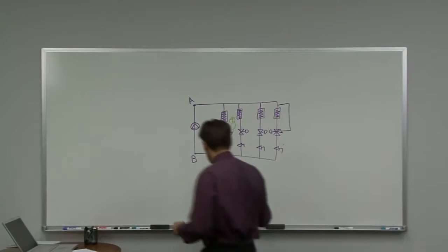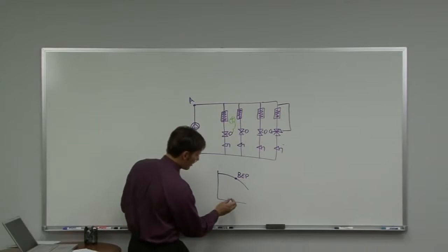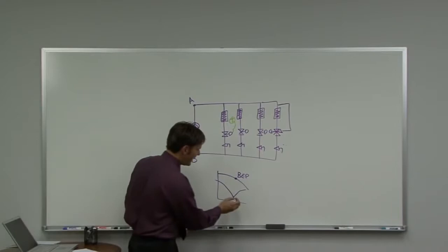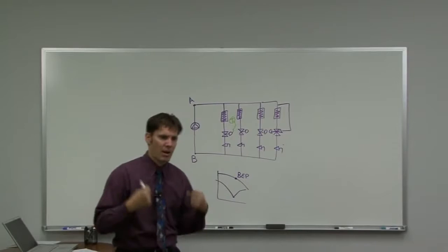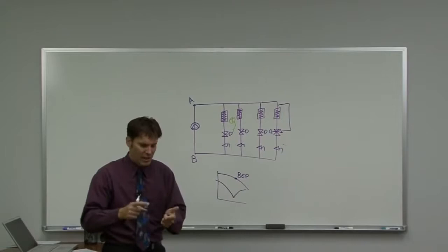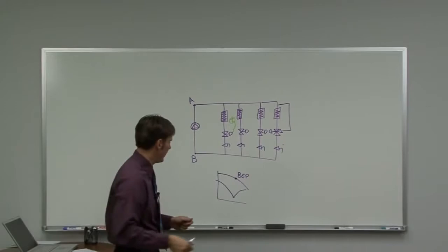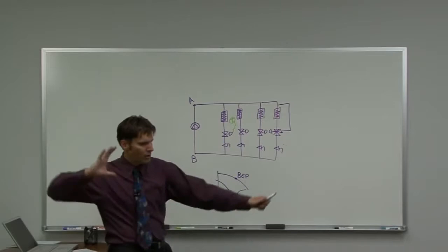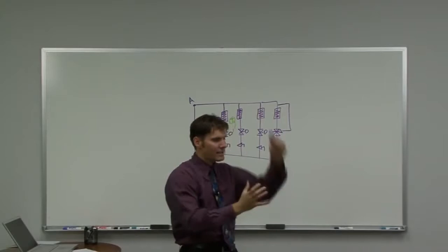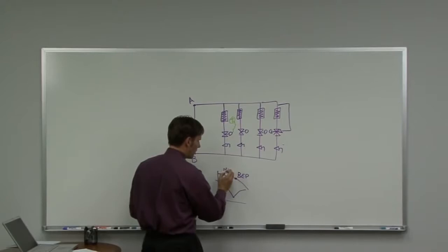When you look at a pump curve, per ASHRAE, you have your best efficiency point. There's a curve in the ASHRAE manual showing the axial and thrust forces being driven on the pump. The further away you get from best efficiency point, the more forces on that pump — it will vibrate. If you deadhead a pump at full speed, you're killing your mechanical seals and bearings. I've seen stainless steel shafts snap in half because we deadheaded a pump that was not supposed to be deadheaded.